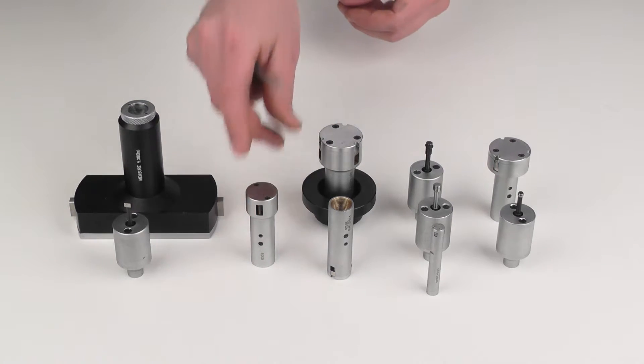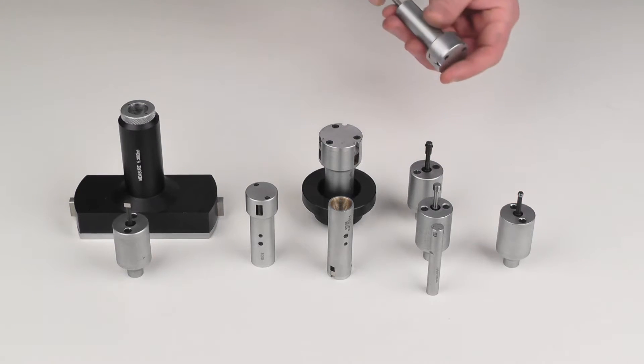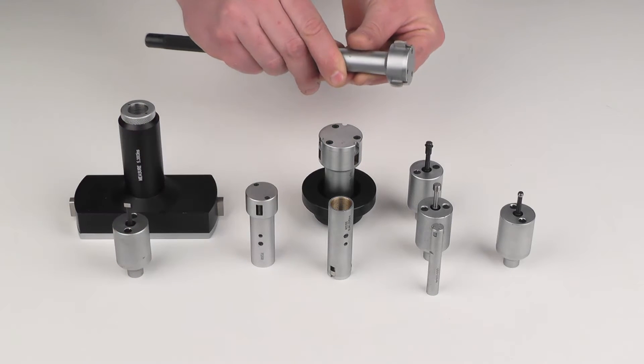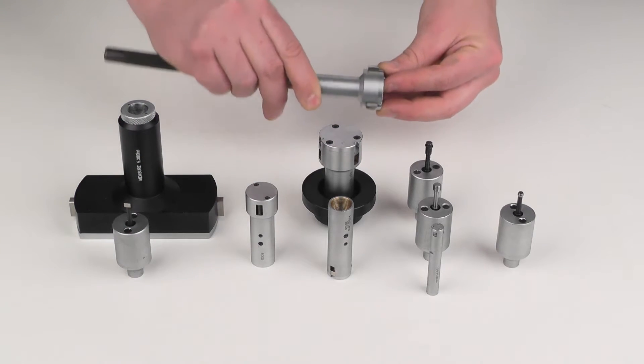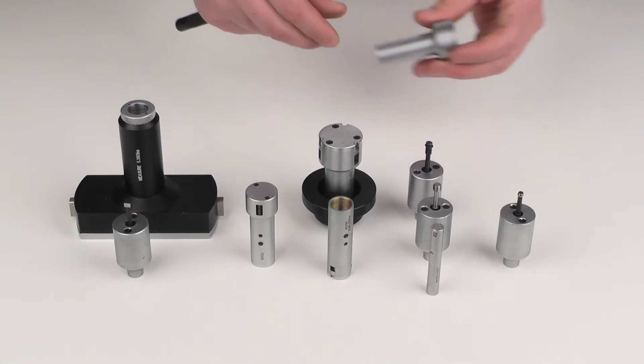So in a little bit more detail, our spherical anvils are intended for deep bore gauging where misalignment is possible. The anvils are cut to a known spherical diameter so that any misalignment does not create a large discrepancy in the value.